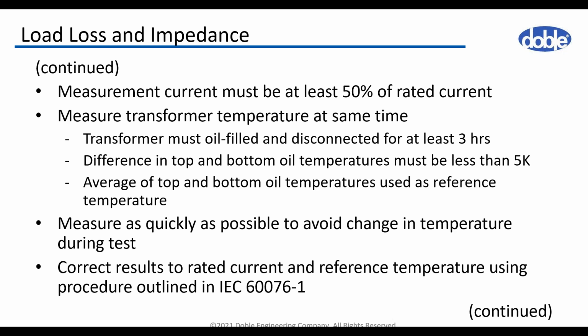IEC recommends to do so after the unit has been filled with oil and without excitation for at least 3 hours, and the difference between the top and bottom temperature is less than 5 kelvins. To obtain this result more rapidly, the liquid might be circulated by a pump if the transformer is, let's say, equipped with pumps, and the reference temperature is the average of the top and the bottom liquid temperature. The measurement should be performed quickly so the temperature rises do not cause significant error.